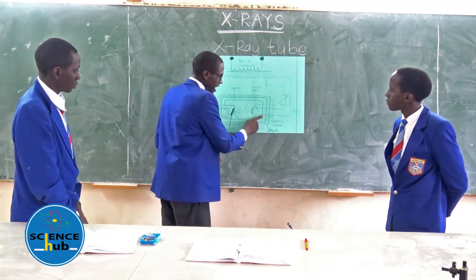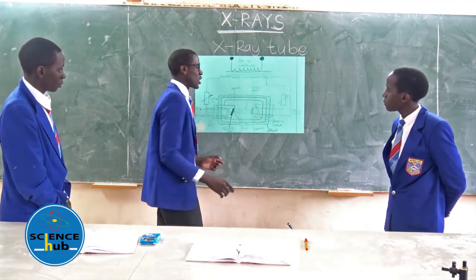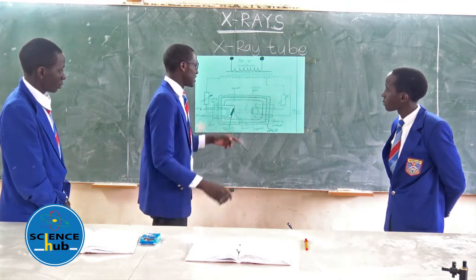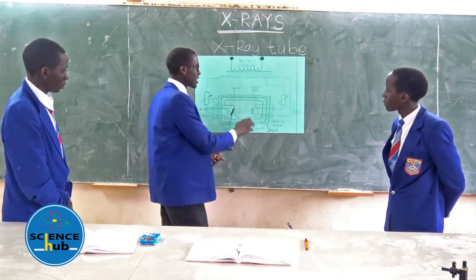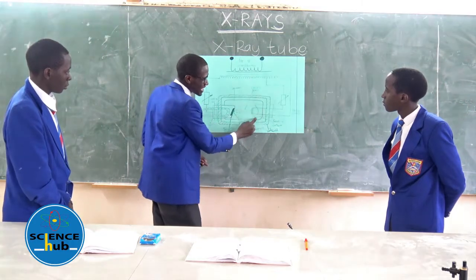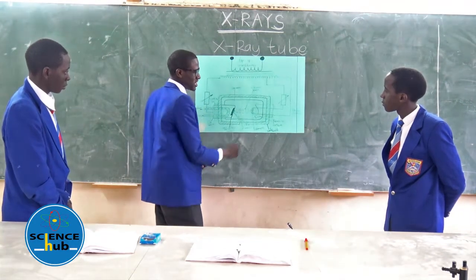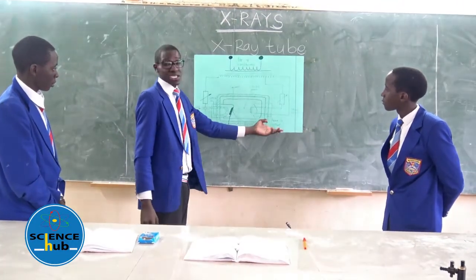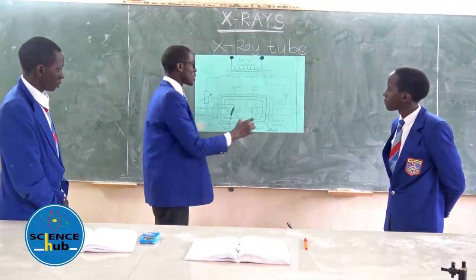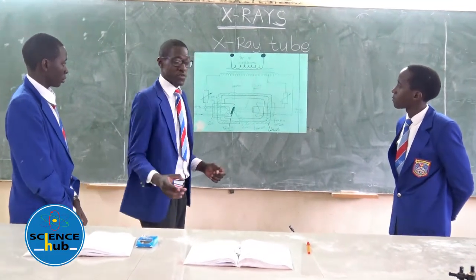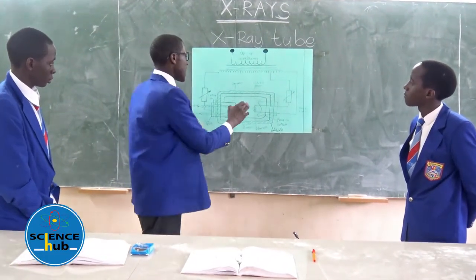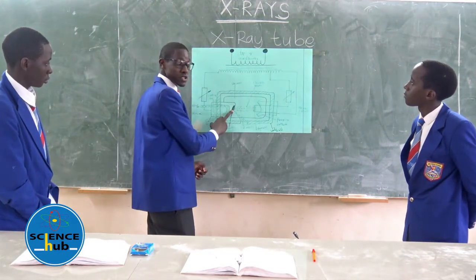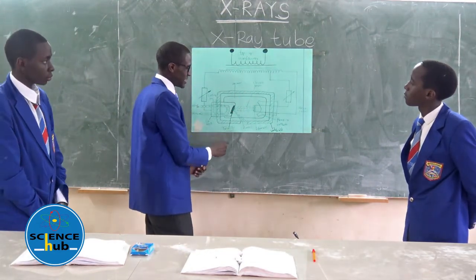At the filament, I also have a cathode, normally negatively charged. The cathode has a concave shape. The concave shape, from just the name focusing cathode, is to allow the electrons to be focused from the filament to the target metal, which is the tungsten target.